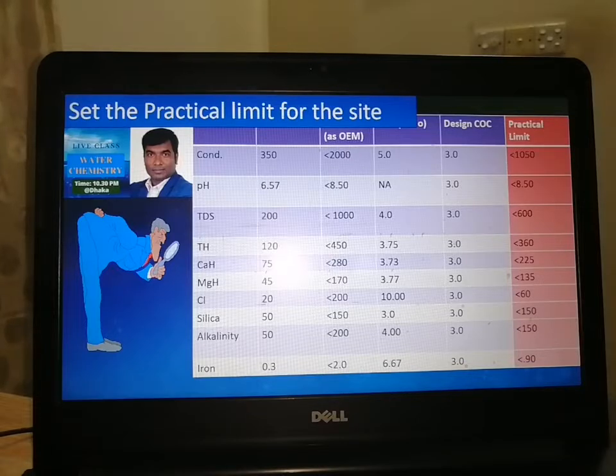You asked a question, how will I reduce silica? Basically, if we have higher silica at the feed water, like 50 or above, usually only the RO system or DM plant can reduce this silica. If it is a cooling tower, usually it's difficult to install an RO plant as a pre-treatment unit. So people manage water properly and try to maintain silica below 150. But sometimes we have to reduce silica at the raw water, and in that case we can use an RO plant or a DM plant.